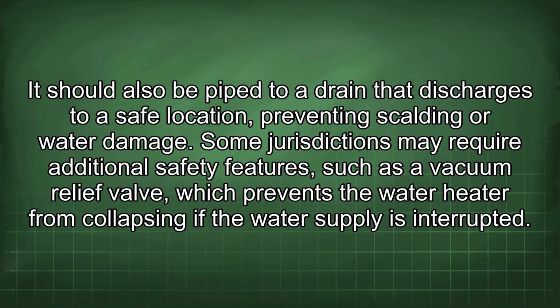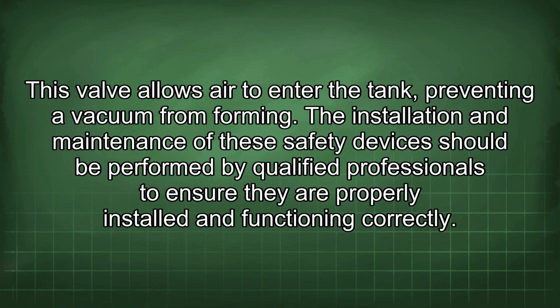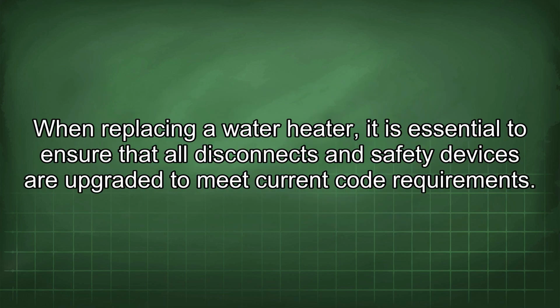Some jurisdictions may require additional safety features, such as a vacuum relief valve, which prevents the water heater from collapsing if the water supply is interrupted. This valve allows air to enter the tank, preventing a vacuum from forming. The installation and maintenance of these safety devices should be performed by qualified professionals to ensure they are properly installed and functioning correctly. When replacing a water heater, it is essential to ensure that all disconnects and safety devices are upgraded to meet current code requirements.